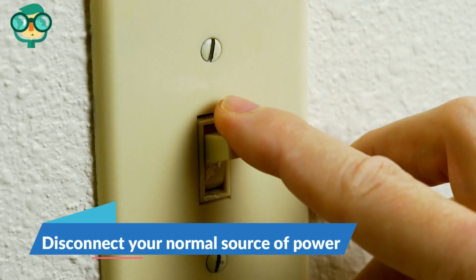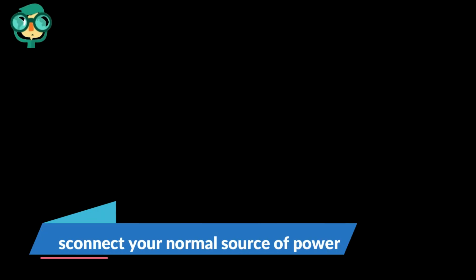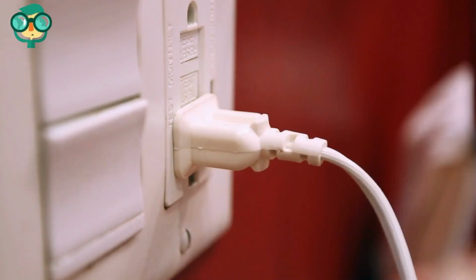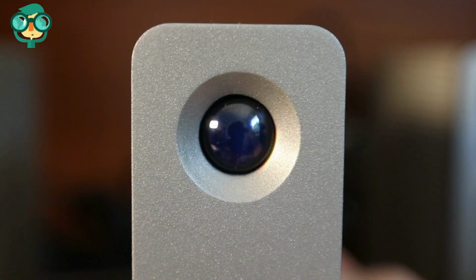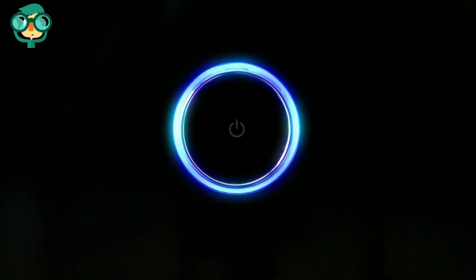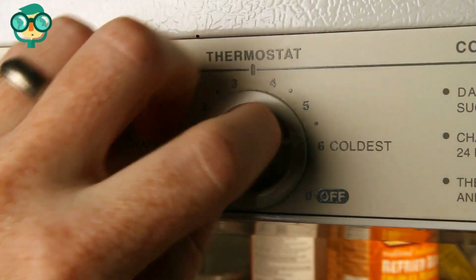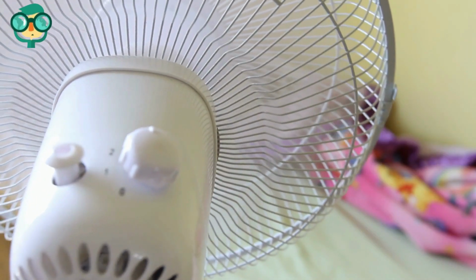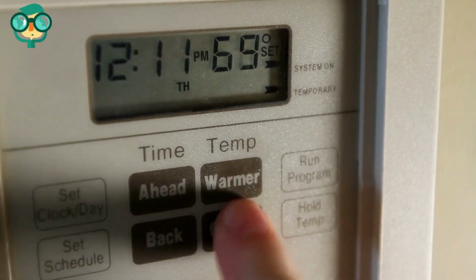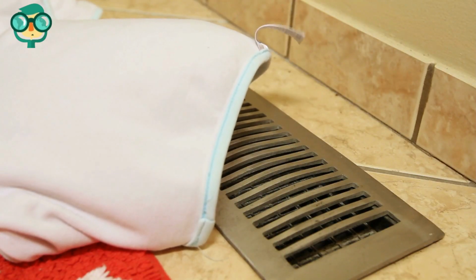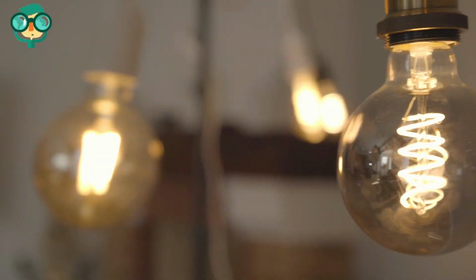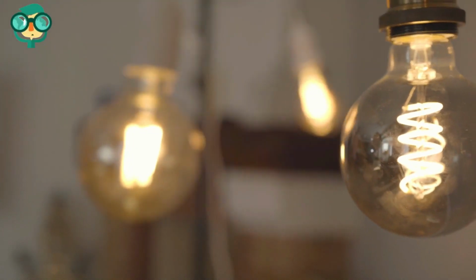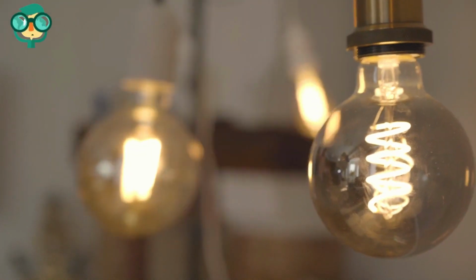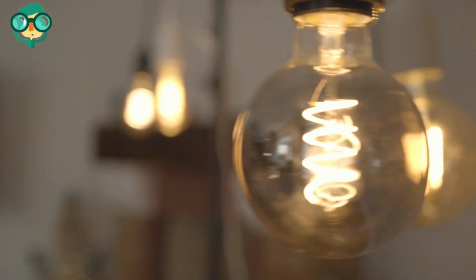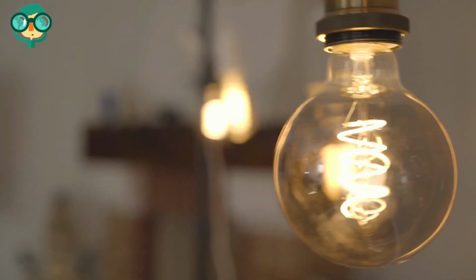Number 2. Disconnect your normal source of power. Even if you've lost electricity, you still need to disconnect your normal source of power by turning the main breaker or fuse off before plugging the generator into a household circuit. If you don't, the electrical current could reverse, go back through the circuit to the outside power grid, and energize power lines or electrical systems in other buildings to at or near their original voltage, without the knowledge of utility or other workers. This backfeed could electrocute utility workers or people in neighboring buildings.